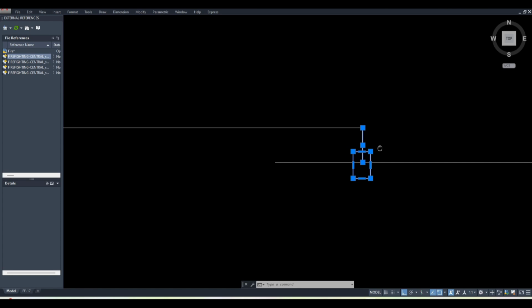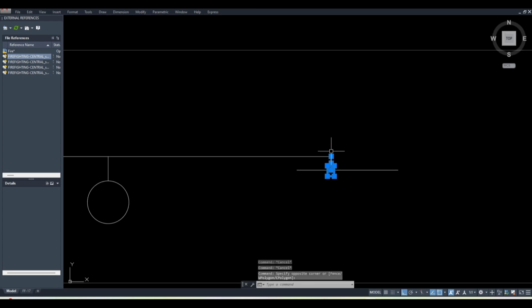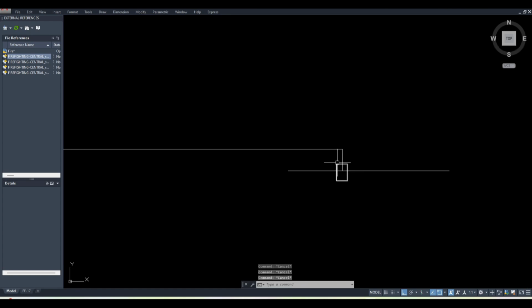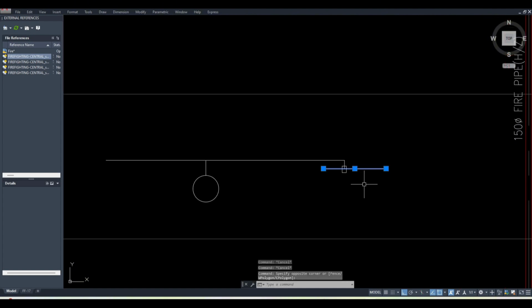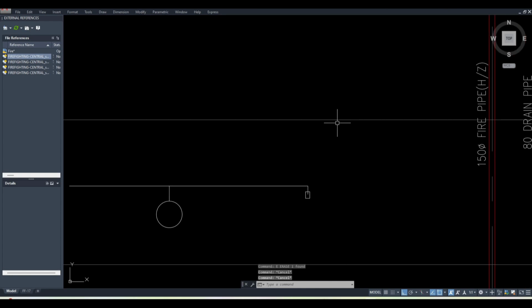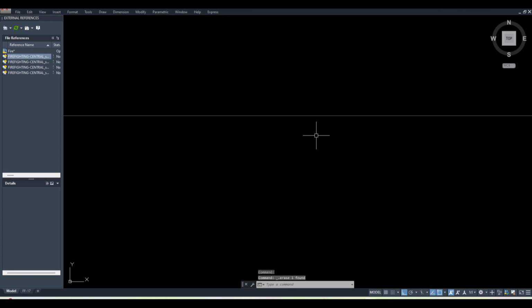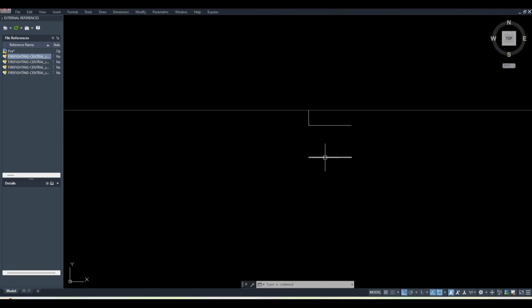Okay, so now you understand the criteria to install this from the soffit. For example, where there is a ceiling you will keep a pendant, but suppose there is no ceiling, then you have to install this within the 25 to 300 distance. It means the distance from the soffit to your sprinkler should not be less than 25. So from here to here, the distance between the soffit and your sprinkler must be 25 away. It cannot be closer, like you cannot touch the roof, your slab, directly. So it has to be 25 away. Also you cannot go too far, which is 300. So the ideal place to install your sprinkler is 25 away, but within 300 away, the range from the soffit.